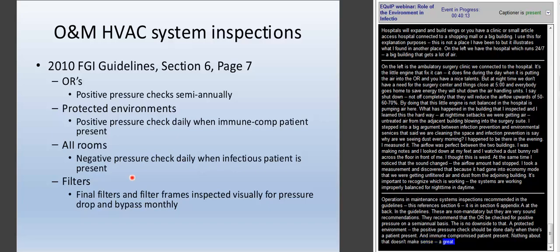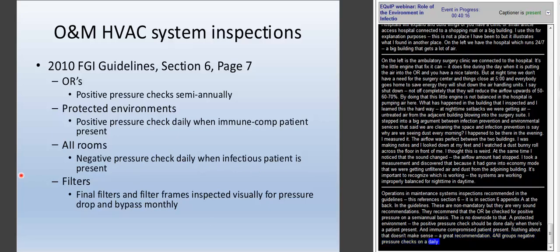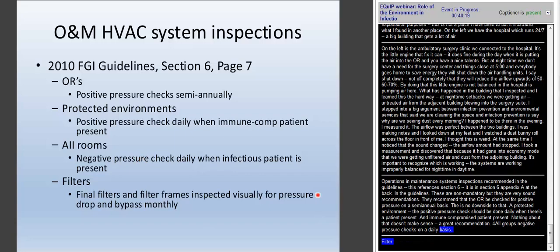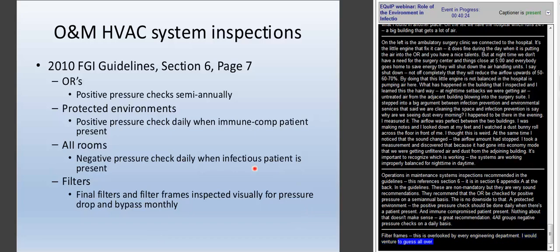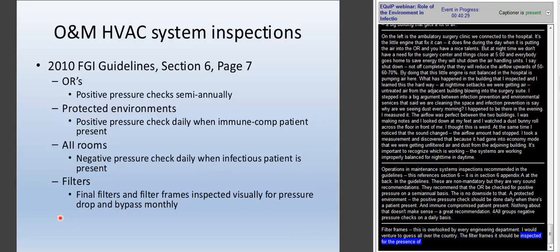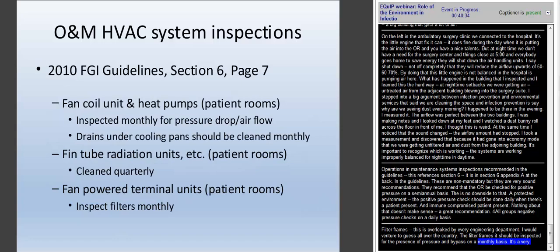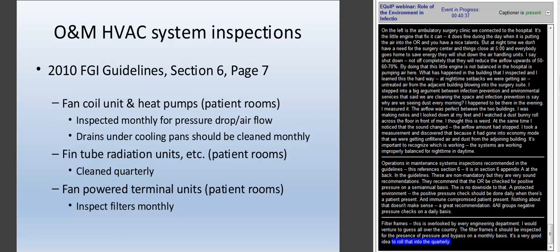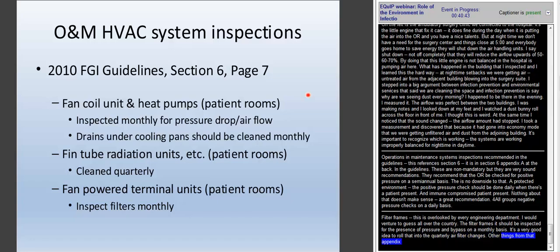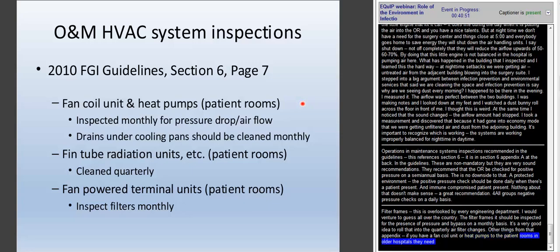And that filters and filter frames, and this is overlooked by pretty much every engineering department, I would venture to guess almost in the country, that final filters and filter frames be inspected visually for the presence of pressure drop and bypass on a monthly basis. That's a very, very good idea, and you can roll that into the quarterly air filter changes. Other things from that same appendix: if you have what's called a fan coil unit or heat pumps that serve patient rooms, which you'll find in our older hospitals, they need to be inspected monthly for pressure drop and airflow, and the drains under the cooling pans be checked for moisture and make sure that they're cleaned monthly.